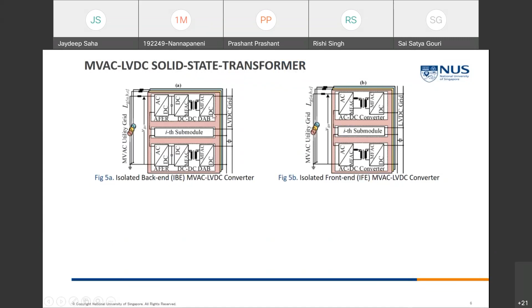Now, what are the drawbacks of this? You would have lower efficiency because of two-stage conversion, and you have low power density. And why is it so? You need a bulky electrolytic capacitor here, which needs to cancel the second harmonic ripple, right? If it's 50 hertz here, then you need to filter out the entire 100 hertz ripple. If you do the calculations, it will be quite bulky, the most bulky element in your entire topology. Electrolytic capacitors are also failure prone, so the reliability will also be pretty low.